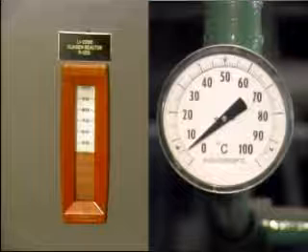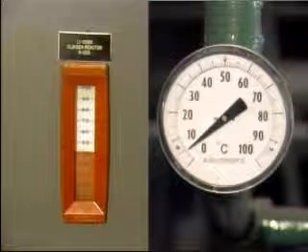Now, if the indication of a value falls between two subdivision marks, it's usually okay to estimate the reading by selecting a number between the two subdivision values. Indicators and gauges both indicate the value of a process variable at the time of the reading. But another instrument, a recorder, indicates the present value of a variable and provides a continuous, permanent record of the value over a given period of time.